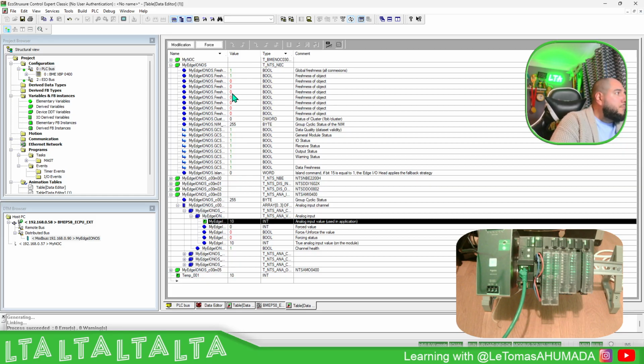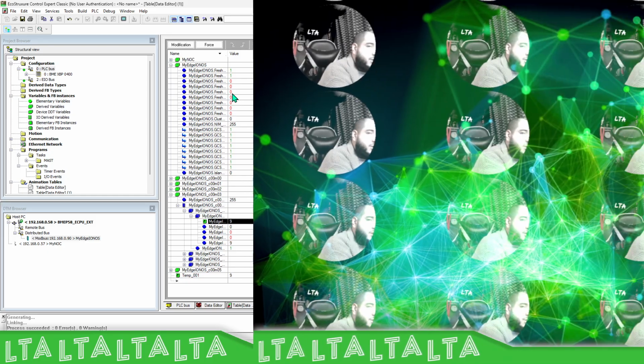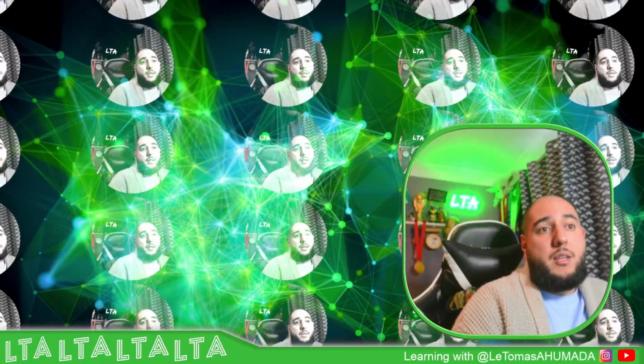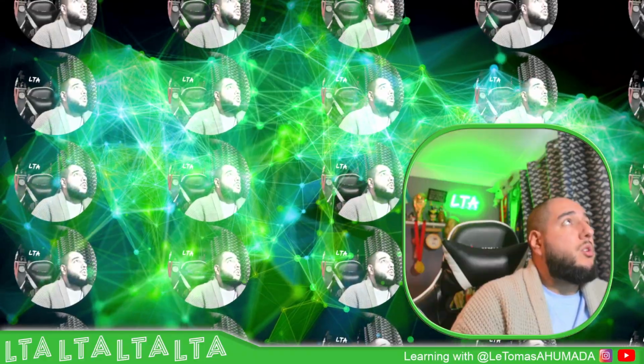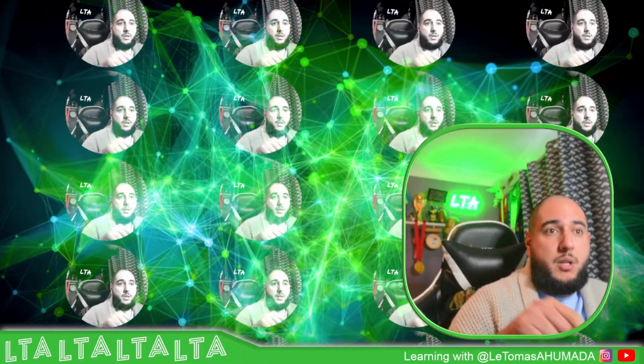Okay, so in this particular case, I'm using the NOS as a switch in order to have this capability of IO scanning the network instead of using the CPU, and using the EdgeIO as a DIO in this particular case. So as you can see, it's very straightforward. Instead of using a NOC, you can use the NOS in order to make the scanning of the network. So what we're going to do later is to use it as a RIO. We're going to use the dual port on the M580 to create a RIO network, and then the RIO network would be the Modicon EdgeIO.